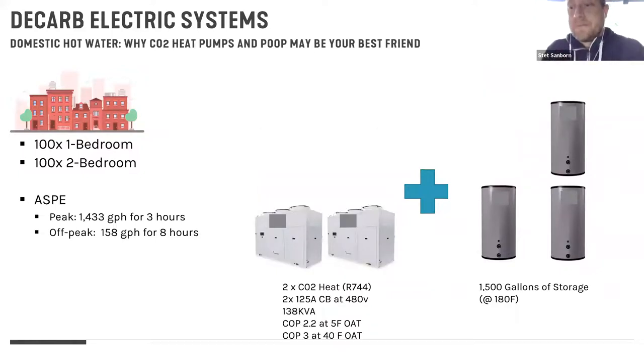The next chunk is, what if I go to the new heat pumps that are coming on the market? And these specifically are CO2 heat pumps. So they're using CO2 as a refrigerant, R744, which is great because the refrigerant itself has a global warming potential of 1. So even leakage isn't as big of a concern. But these operate at really high pressures. There's not a lot of choices on the market. There's a couple more coming on next month, which I'm super excited about.